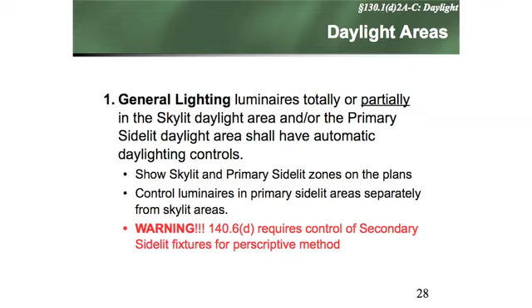Most engineers use what's called the prescriptive method. And the code says in the prescriptive method section, if you use this method, you also have to have automatic daylighting controls for the secondary side lit zone. So this room is a perfect example, where you'd have daylighting controls to be able to lower that one down based on whether or not the shades were open, and this one down a little less. So there's some requirements about it. They say, well, the daylighting controls have got to lower it based on the table that we saw, the multi-level.